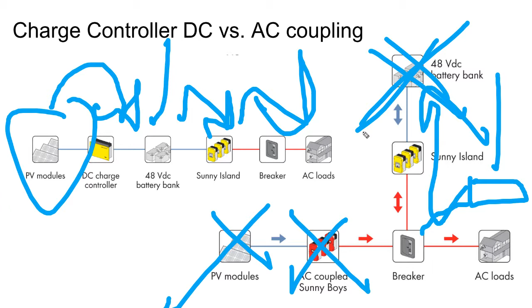The industry really needs to stop talking about whether DC coupling or AC coupling is better, because the price difference between the inverter and the charge controller is very close. If you're grid tied and retrofitting a batteryless system with batteries, AC coupling is probably the cheapest way to do it. There's a slight cost and efficiency advantage to DC coupling, and as the off-grid market heats up that advantage should become more clear, but right now the off-grid residential market is still in its infancy, so AC versus DC coupling is very close together.